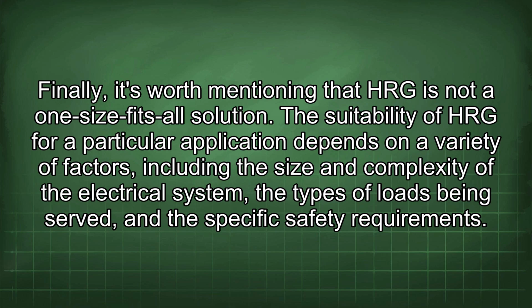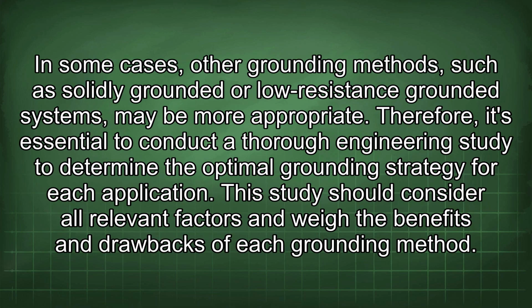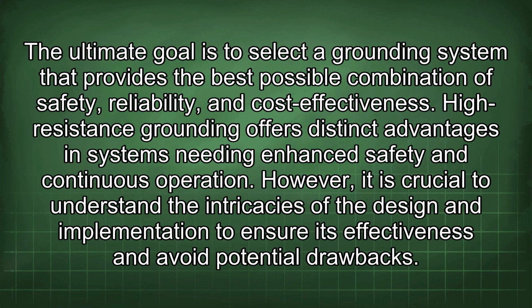Finally, it's worth mentioning that HRG is not a one-size-fits-all solution. The suitability of HRG for a particular application depends on a variety of factors, including the size and complexity of the electrical system, the types of loads being served, and the specific safety requirements. In some cases, other grounding methods, such as solidly grounded or low-resistance grounded systems, may be more appropriate. Therefore, it's essential to conduct a thorough engineering study to determine the optimal grounding strategy for each application. This study should consider all relevant factors and weigh the benefits and drawbacks of each grounding method. The ultimate goal is to select a grounding system that provides the best possible combination of safety, reliability, and cost-effectiveness.